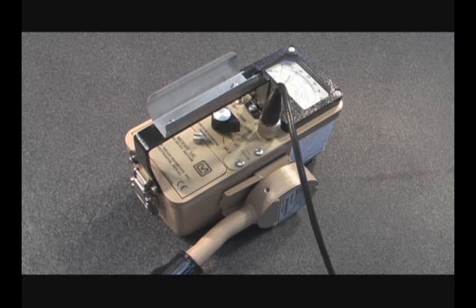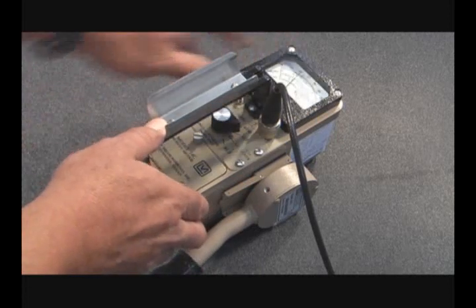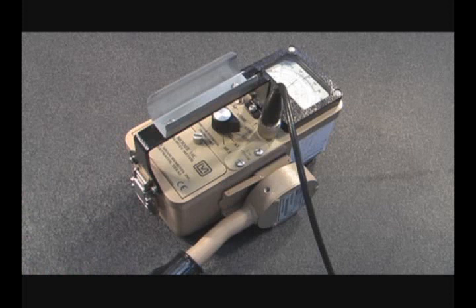The slow position should respond approximately 5 times slower than the fast position. Toggle the fast-slow switch back to the fast position. The slow response position is normally used when the instrument is displaying low numbers, which require a more stable meter movement. The fast position is used at medium to high rate levels.